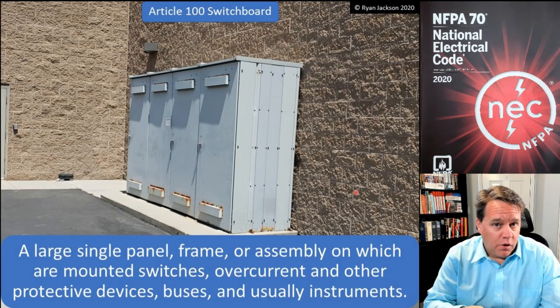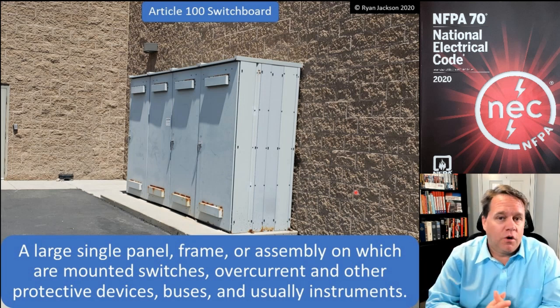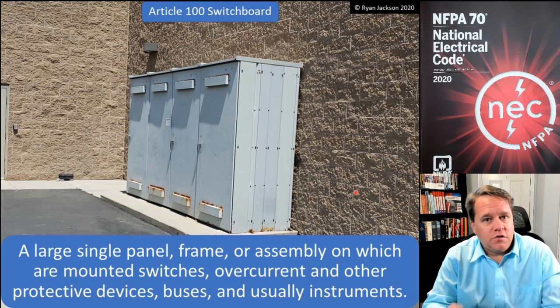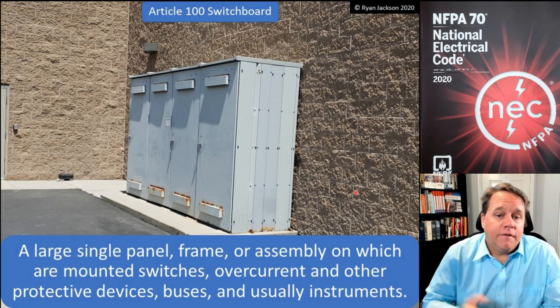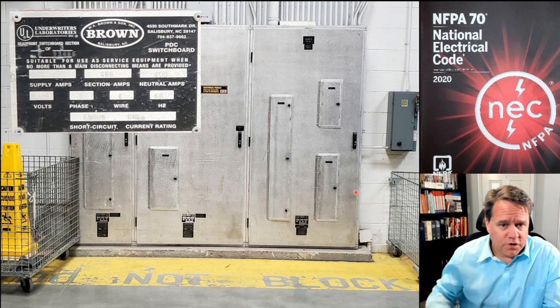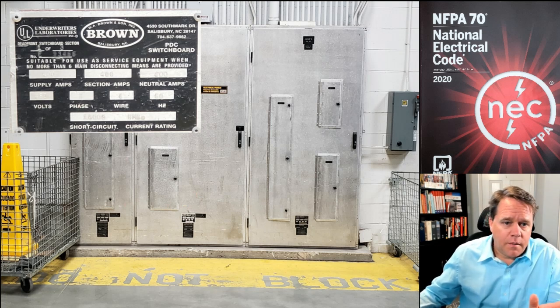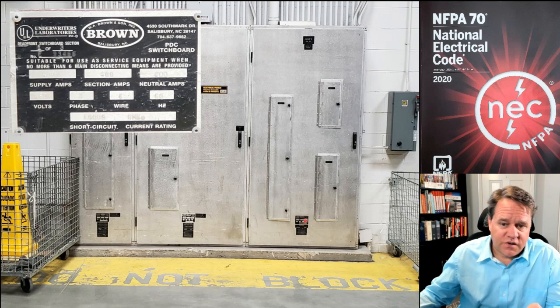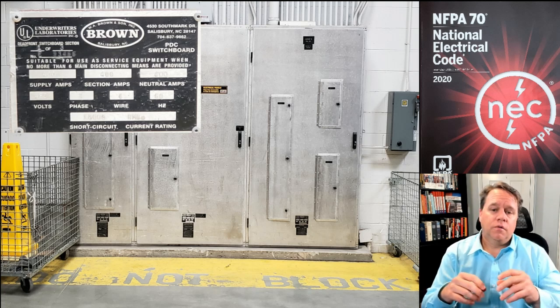So a panel board is a single panel installed in a cabinet or cutout box. A switchboard is bigger, generally speaking — it's a large single panel, frame, or assembly on which are mounted switches, overcurrent and other protective devices, buses, and usually instruments. What we're looking at in this photograph is a switchboard. Here's another example — if you squint you can read that it says 'dead front switchboard, section one of three,' so those three sections together create a switchboard.